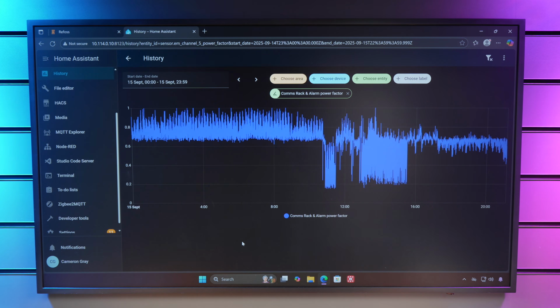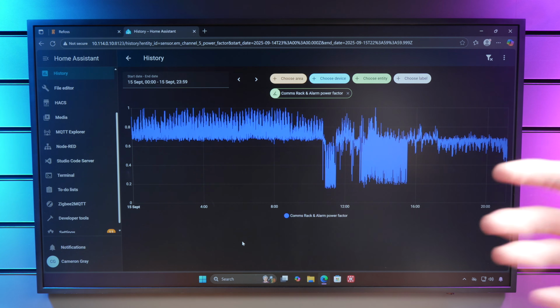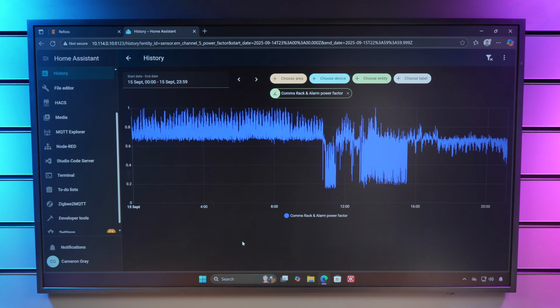However, we do have a problem. With my initial demo, I talked about that issue with the power factor fluctuating around. I was hoping when I got it all fully installed, that would stop happening once there was load on all the CTs and things like that. Unfortunately, that's not the case, and I'm getting some really weird behaviour with the power factor measurements.